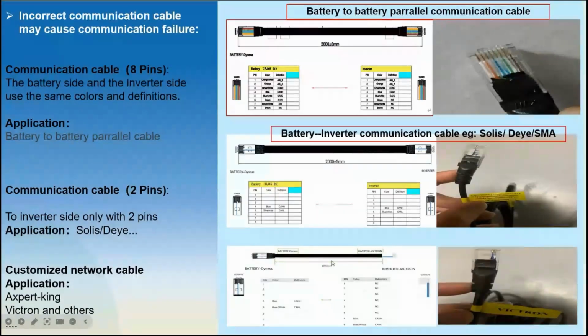So when there is a communication problem, we first need to check the dip switch, and then confirm whether the cable we used is correct. All the cables should be given in the packing list. And if there is a special inverter with no communication cable, the installer can make a new communication cable. We also have an SOP for connecting the battery to any other brand of inverter, and it includes the cable definition, so you can follow the definition to make a new cable. Okay, this is about the communication cable.